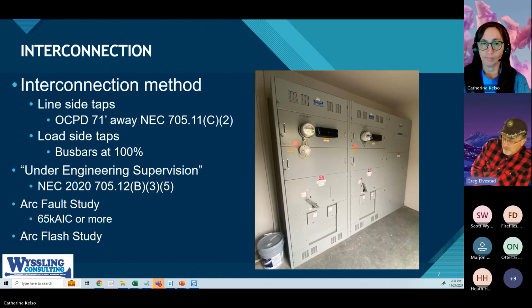There is enormous fault energy possible from the array being delivered to the grid at the point of interconnection. So when dealing with system design, you have not only the arc flash energy the power company transformer can deliver on the secondary side, but also an enormous amount of energy that can be pumped into a short circuit at any point along the interconnection path. It comes from both directions, and when light is on, the modules are active, so you have continuous energy being pumped in.